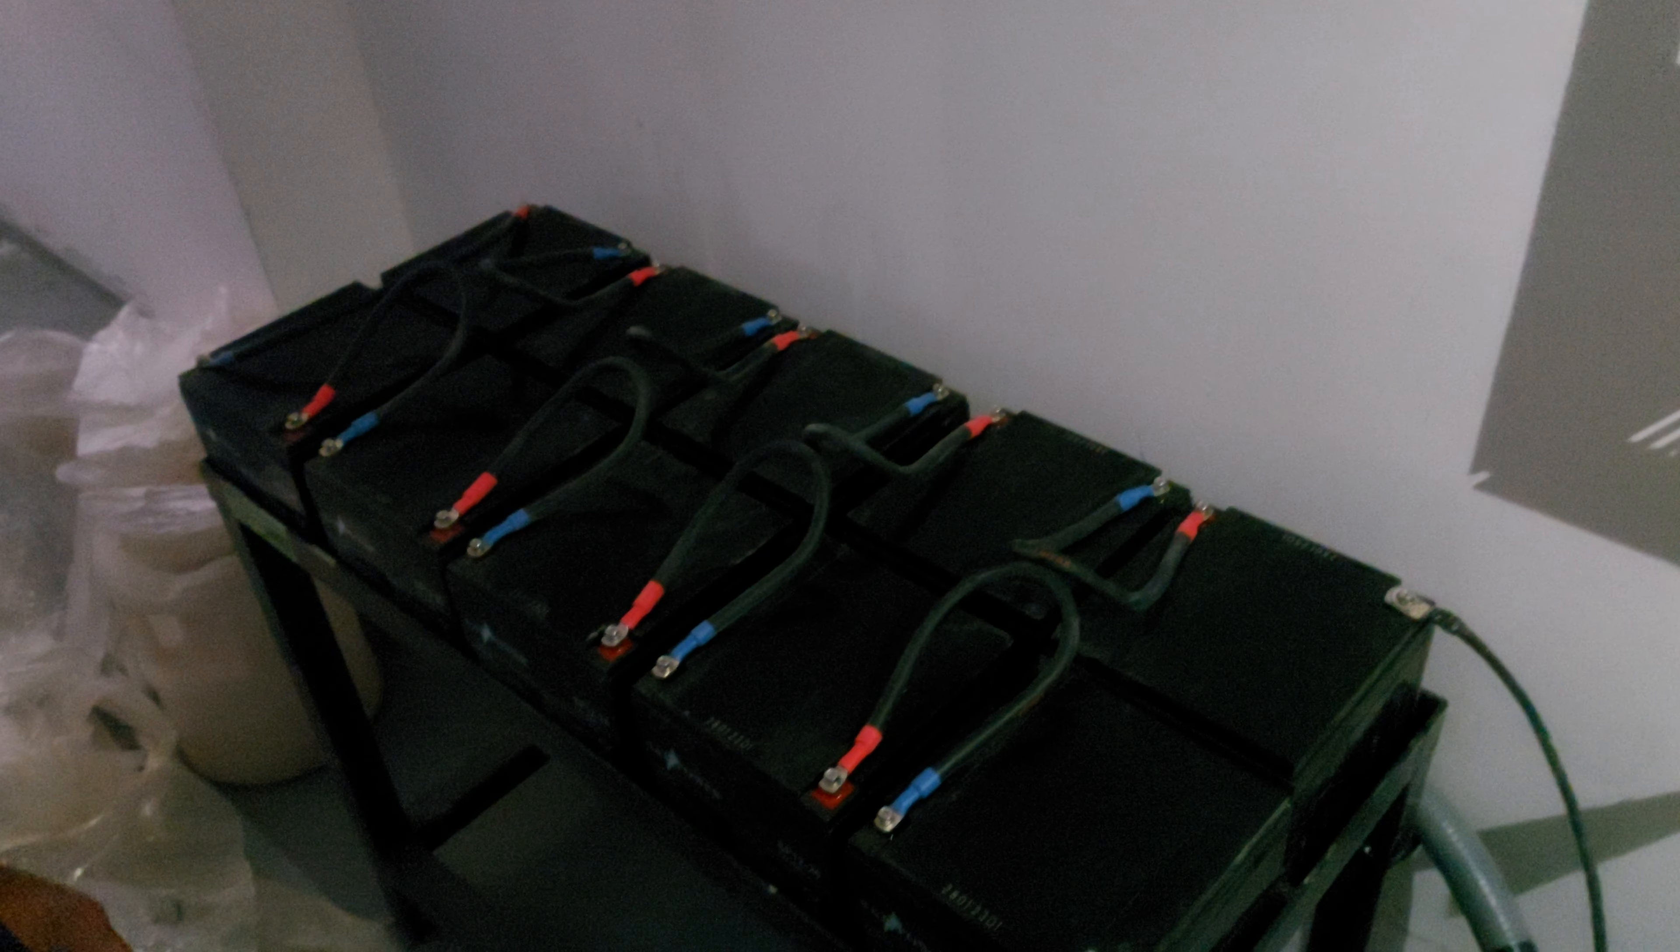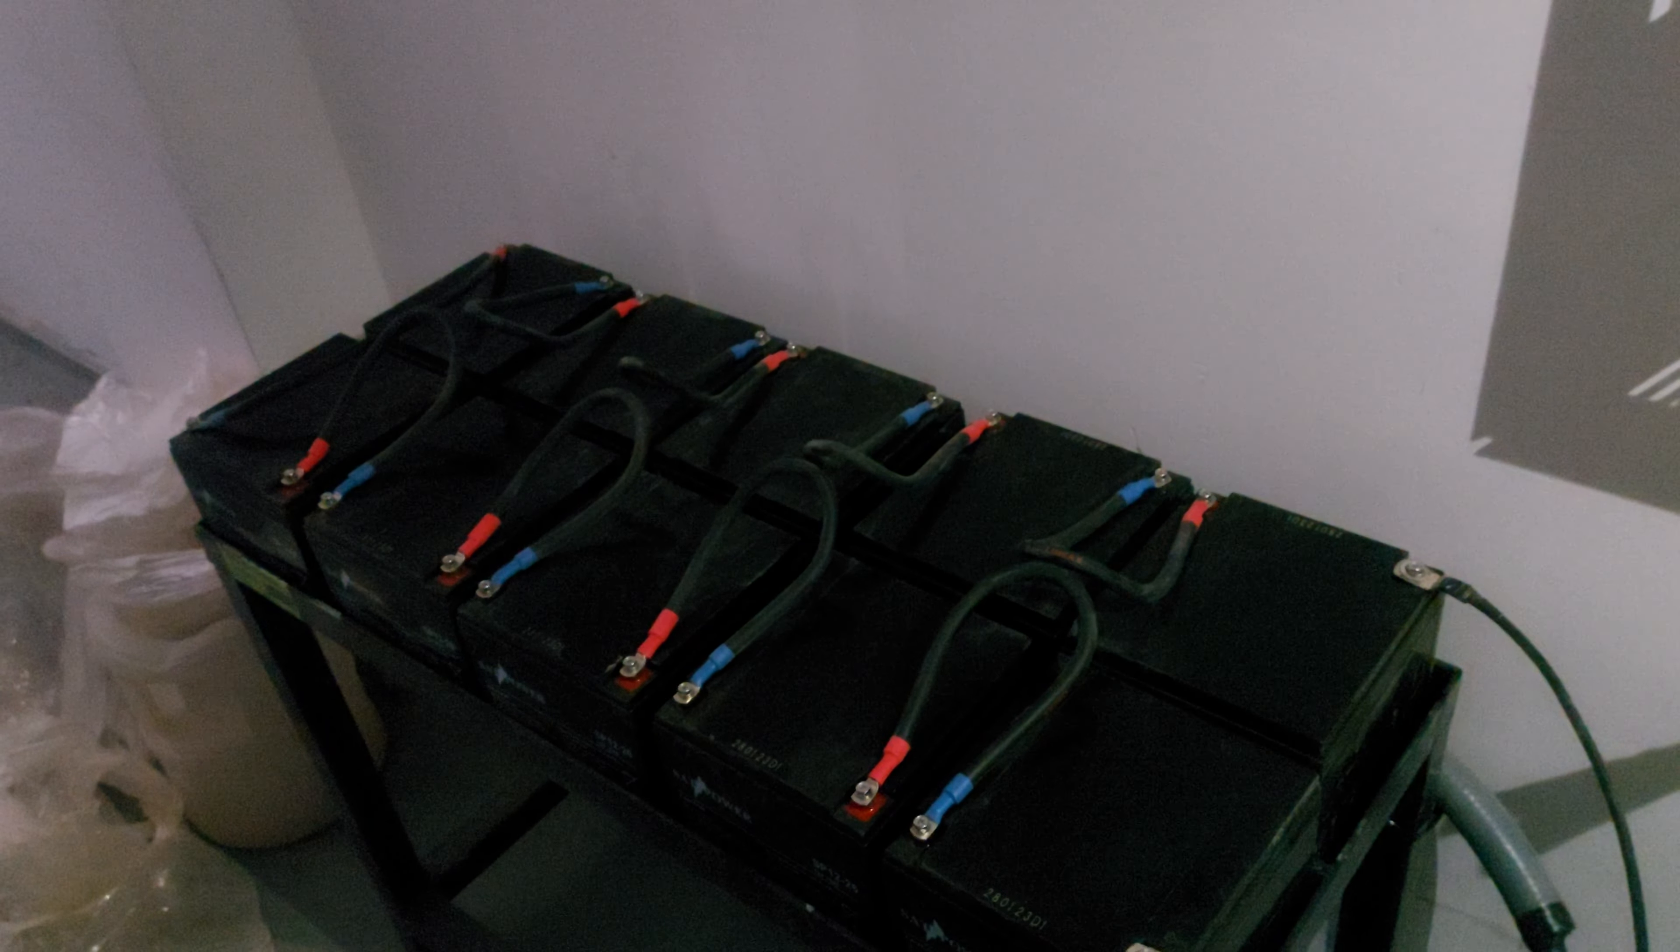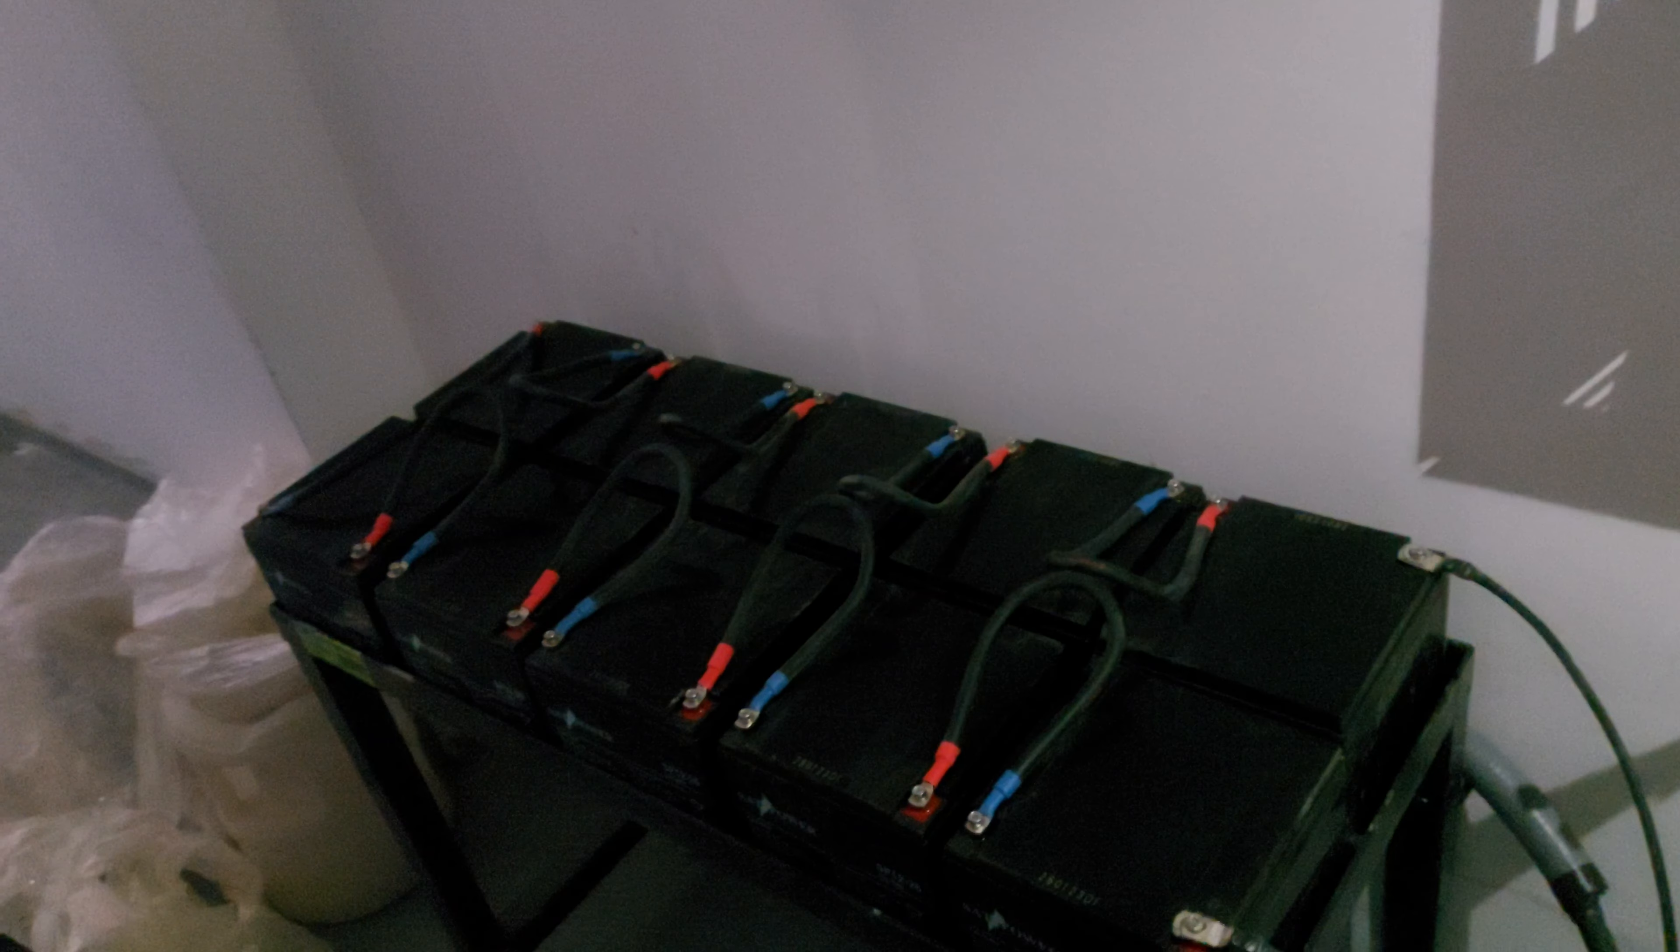Each battery is 12 volt, and we have total 10 batteries. So 10 into 12, it will be 120. In the float mode it will be 13 volts, so it will come in float 136.2.